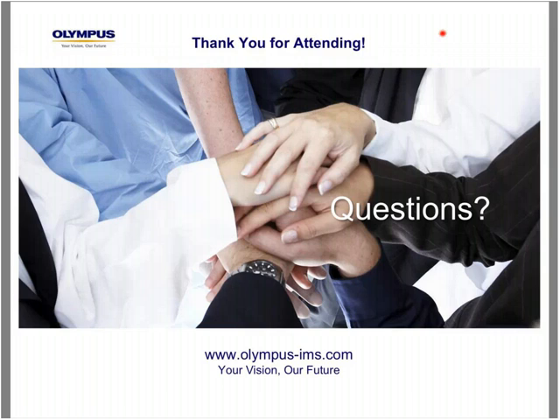So that's the webinar. I want to thank you all for your time. Both Olympus product lines are excellent. Both thickness gauges and flaw detectors are great instruments. And again, it really comes down to the application and what are you measuring. So if you're detecting flaws or voids, checking welds, and you also want to measure thickness, you're going to want a flaw detector. But nothing's going to really beat an Olympus thickness gauge if you want the most accurate, repeatable corrosion thickness measurements. And what's nice is they're small, powerful, less expensive instruments.